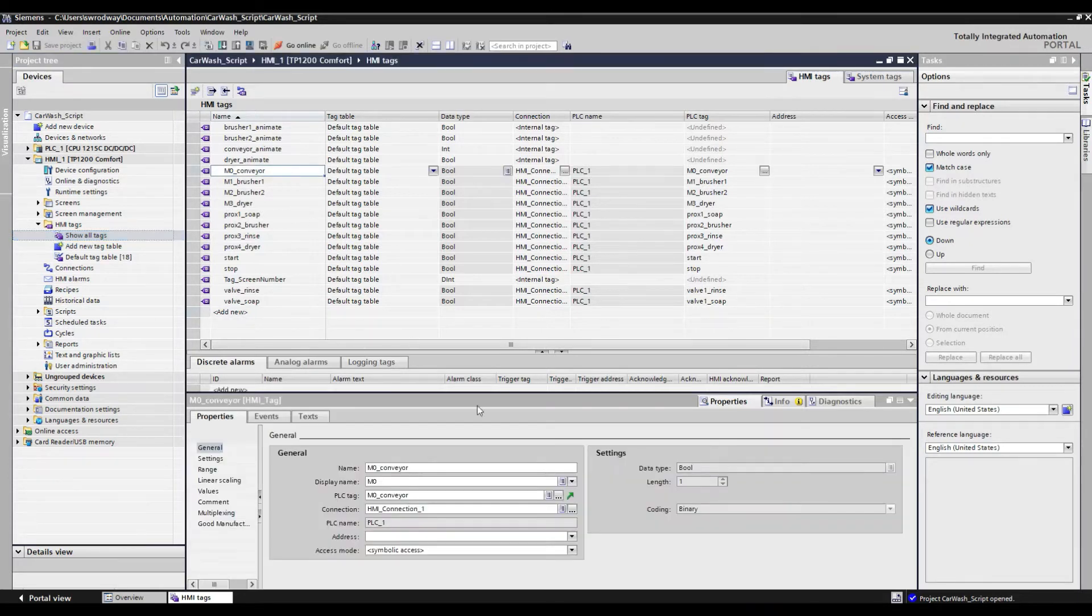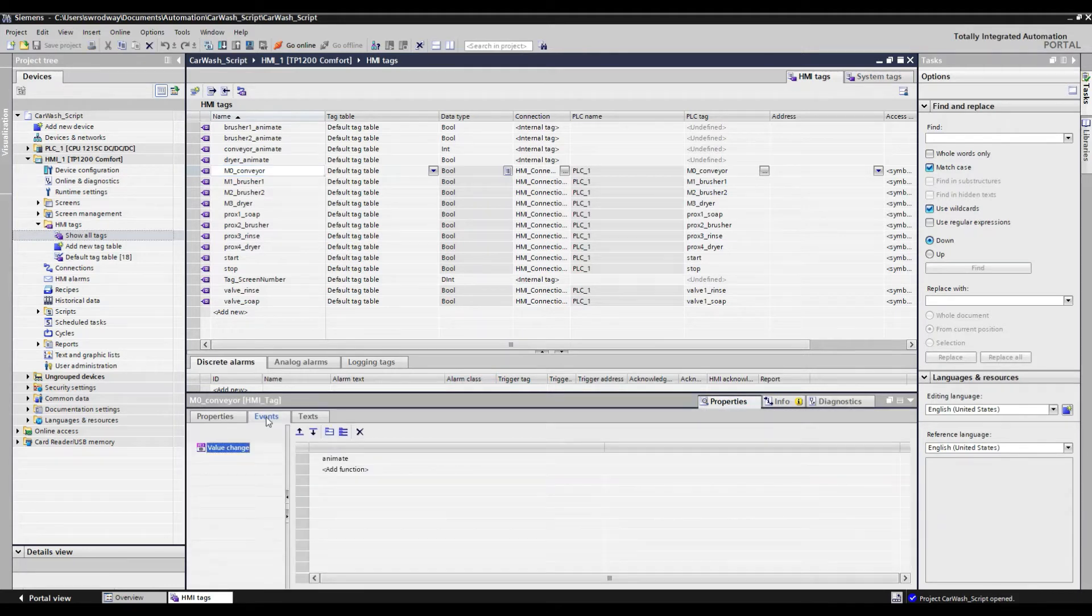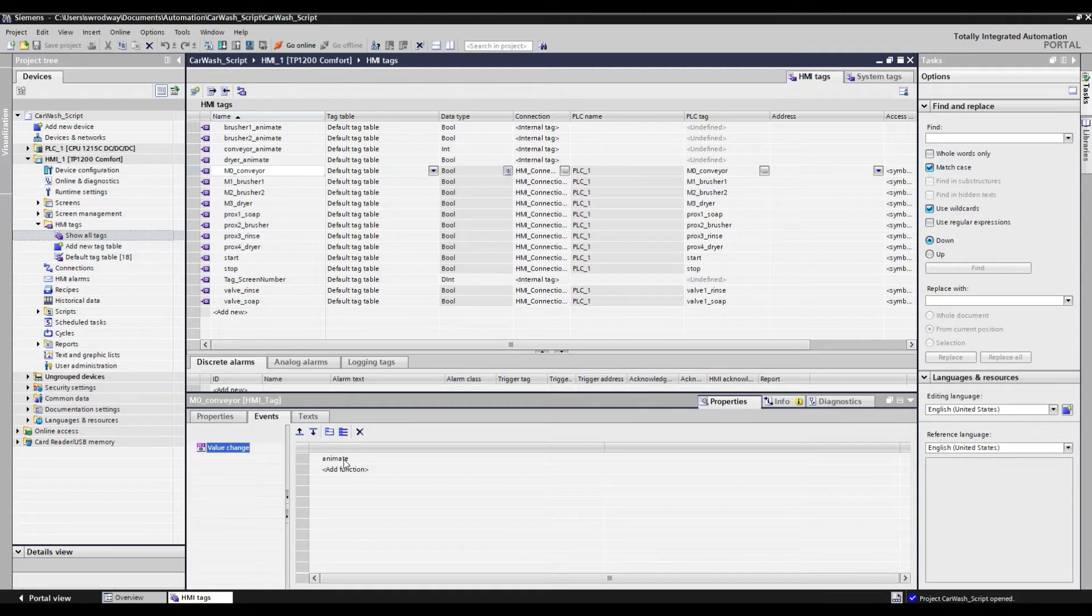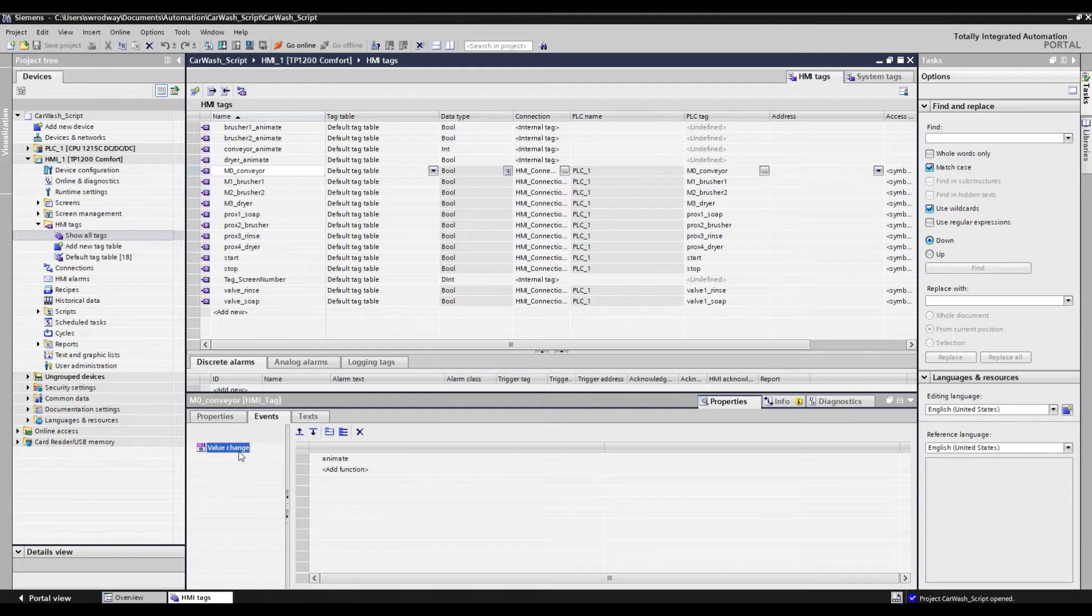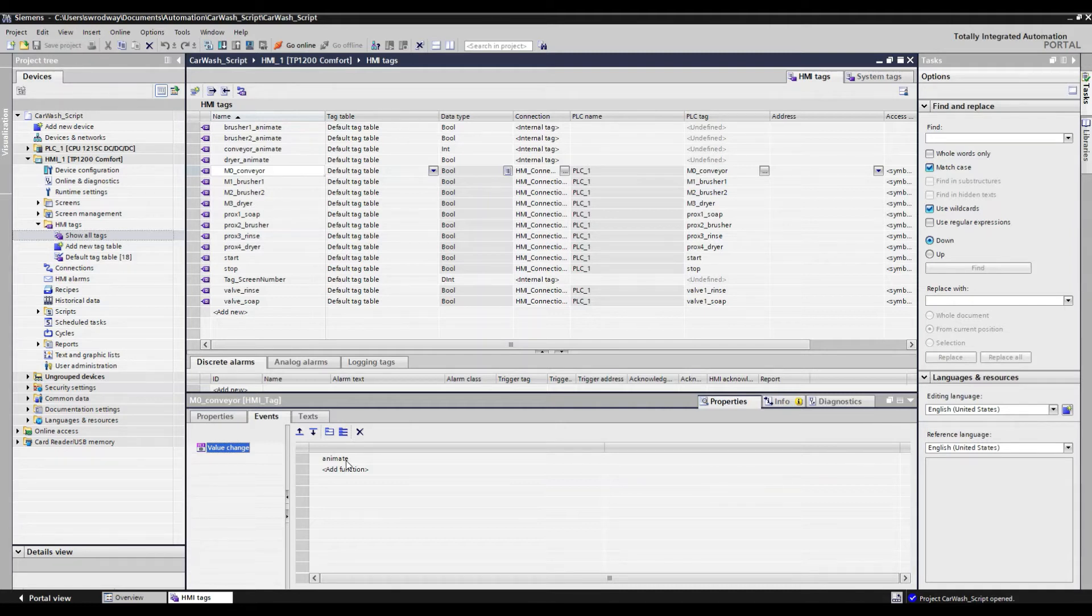We go ahead and select that tag, select its properties, and events. You can see that we have one event option here which will allow for us to call that function. In this case, our VB function named animate. Value change implies that when the bit changes, regardless from high to low or low to high, this function will be called. Because we want to try to simulate the real world, we would really like to only see that called when it goes high. We can do so by setting a parameter inside of our function.